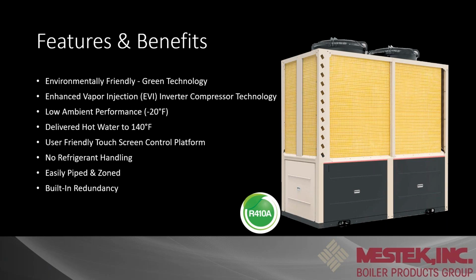So by utilizing a bypass valve, the hot refrigerant vapor on the condenser is bypassed through a heat exchanger, which combines with the colder gas on the evaporator expansion side. So the heat energy is transferred, raising the gas temperature even further, which then injects mid-range pressure into the head of the compressor. So we're taking that hot gas and injecting it into the head of that compressor to gain capacity. With this technology, you'll gain about 20% more capacity at a lower temperature, giving us that heat that is needed, okay? And we'll go through that a little bit more through the presentation.